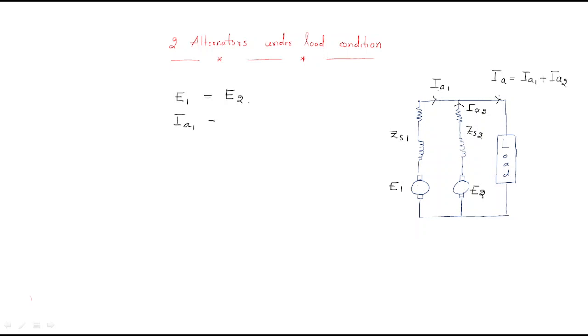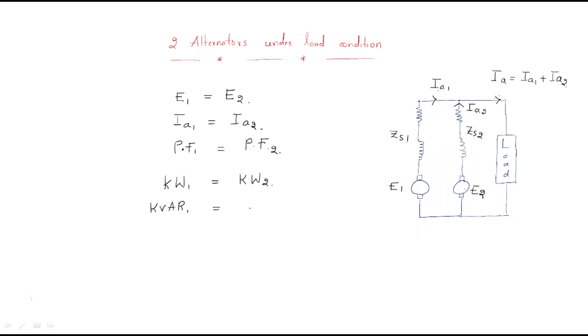Further conditions are: the power factor of machine one (pf1) should equal the power factor of machine two (pf2); the active power generated by machine one (kW1) should equal that of machine two (kW2); and the reactive power generated by machine one should equal that of machine two. All parameters should be equal for proper parallel operation.